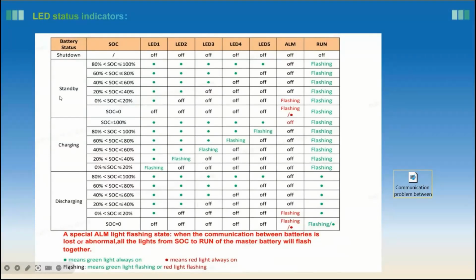When the battery is in standby, the run light will always be flashing. When the battery is charging, it is also flashing. But when the battery is discharging, the run light will always be solid green. When the battery SOC is low, for example from 0 to 20%, the alarm light will flash. And when the battery SOC is 0, there will be a solid or flashing red light, and also there will be beeps on the battery BMS.